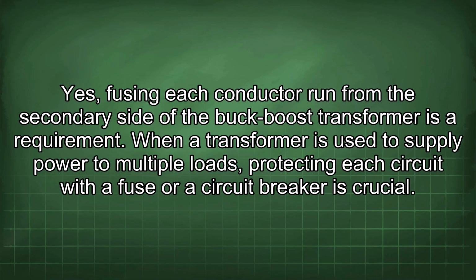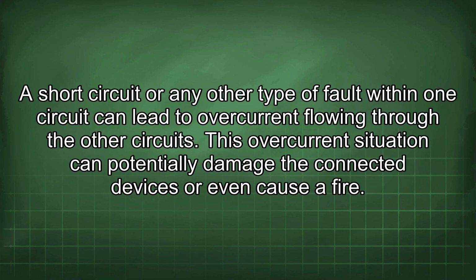Yes, fusing each conductor run from the secondary side of the buck-boost transformer is a requirement. When a transformer is used to supply power to multiple loads, protecting each circuit with a fuse or a circuit breaker is crucial. A short circuit or any other type of fault within one circuit can lead to overcurrent flowing through the other circuits. This overcurrent situation can potentially damage the connected devices or even cause a fire.